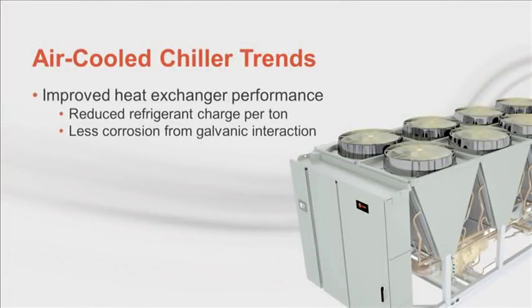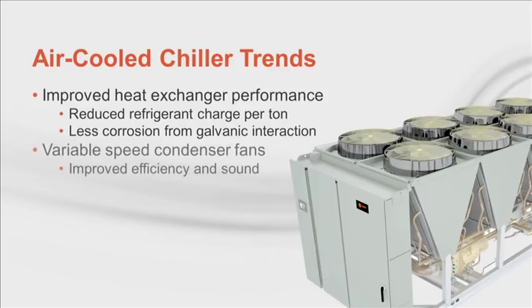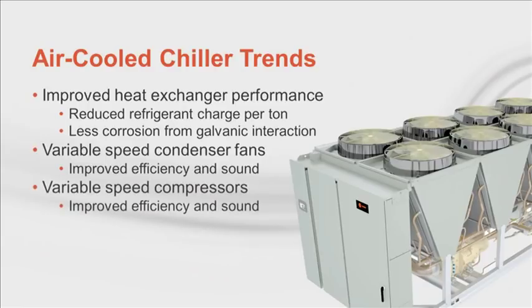Let's discuss 4 trends in today's air-cooled chiller systems: heat exchangers, variable speed, sound attenuation, and chillers as heaters. In heat exchanger design, there is a move toward all aluminum designs, including microchannel technology. The benefit of this is there is less copper to aluminum interaction and a lower required refrigerant charge. Variable speed condenser fans improve system efficiency and sound. And variable speed compressors give more efficiency improvements.